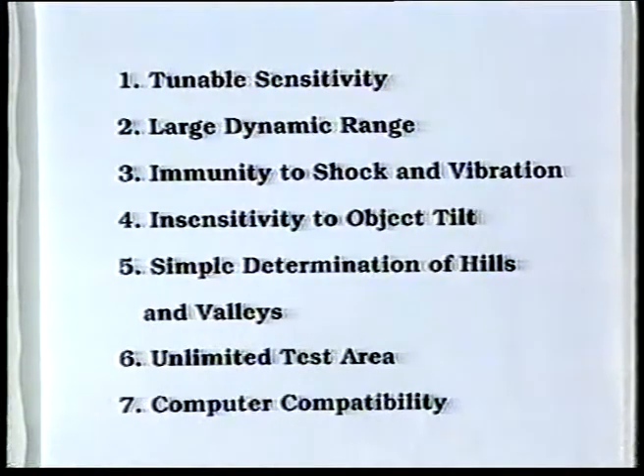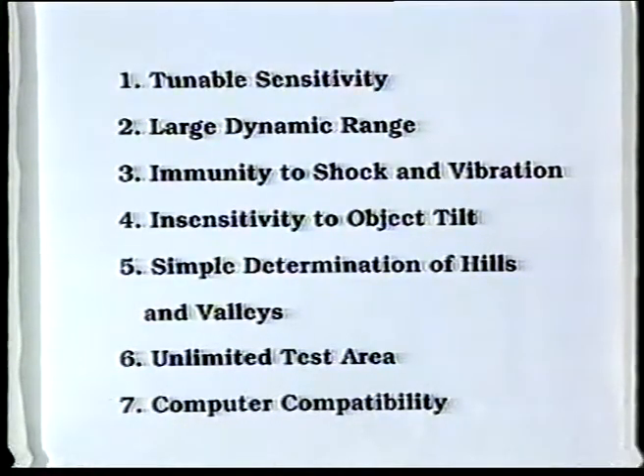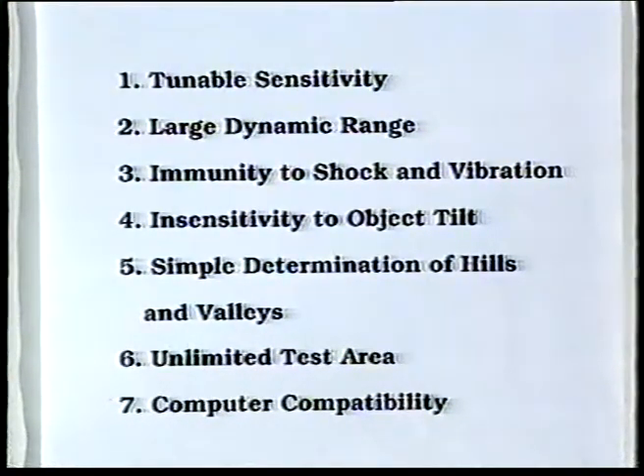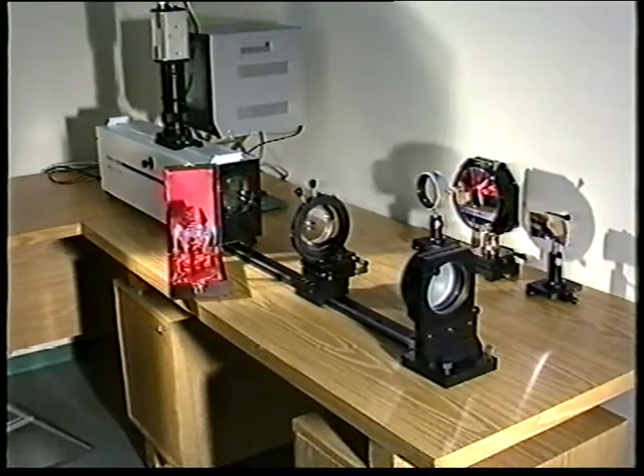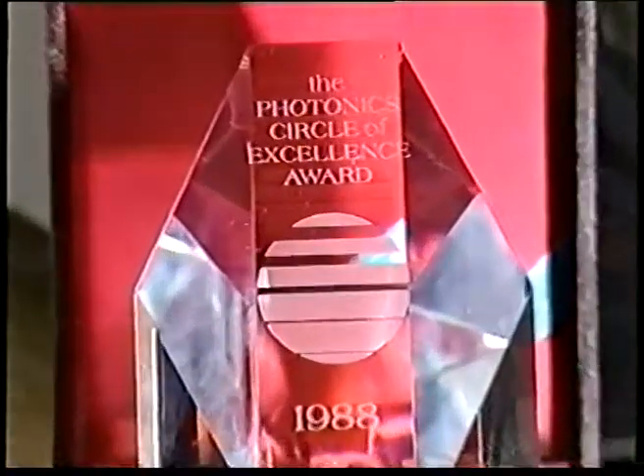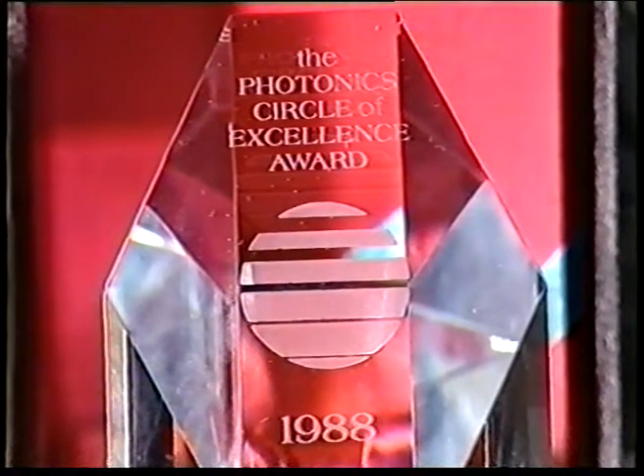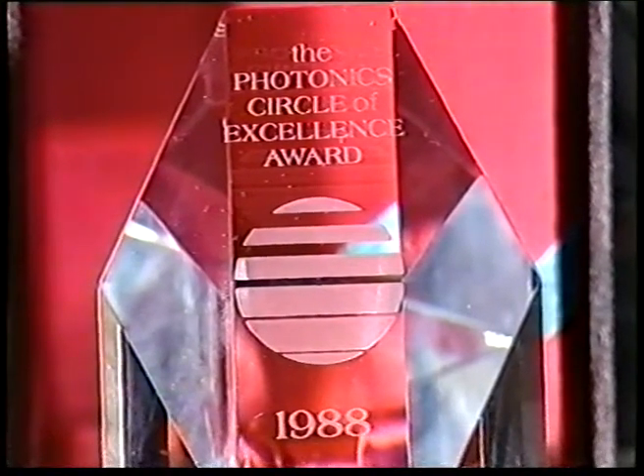To summarize, the advantages of Moiré deflectometry over interferometric techniques are: tunable sensitivity, large dynamic range, immunity to mechanical shock and vibrations, insensitivity to object tilt, simple determination of hills and valleys, unlimited test area, and computer compatibility. Because of all the benefits of Moiré deflectometry, the OMS 400 Moiré deflectometer was chosen by Photonics Spectra Magazine as one of the 25 best new products of 1987. An award-winning breakthrough in non-destructive optical testing.